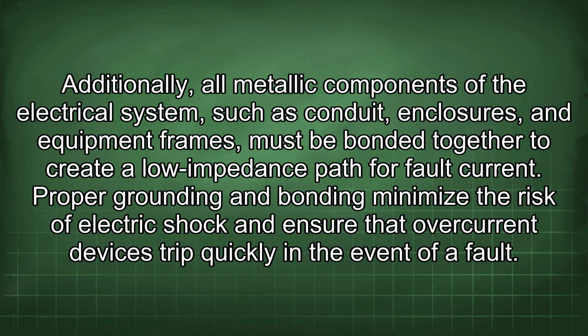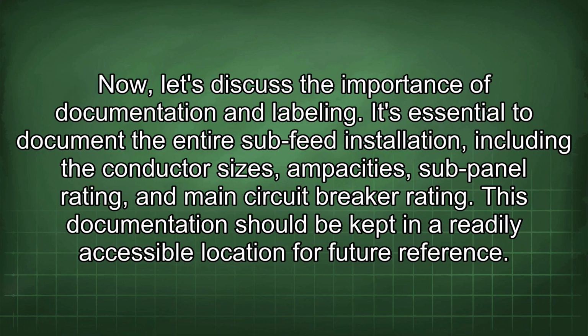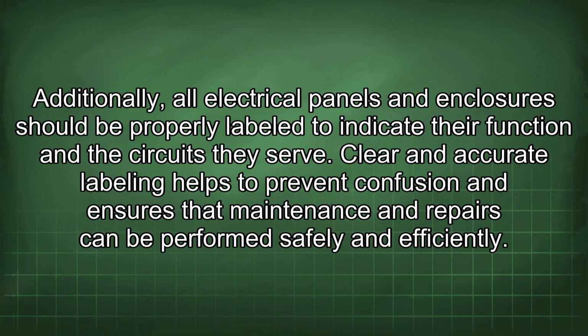Now let's discuss the importance of documentation and labeling. It's essential to document the entire sub-feed installation, including the conductor sizes, ampacities, sub-panel rating, and main circuit breaker rating. This documentation should be kept in a readily accessible location for future reference. Additionally, all electrical panels and enclosures should be properly labeled to indicate their function and the circuits they serve. Clear and accurate labeling helps to prevent confusion and ensures that maintenance and repairs can be performed safely and efficiently.